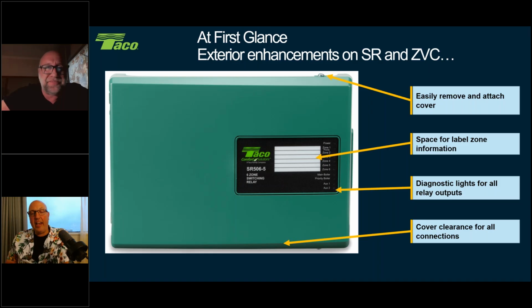Exactly. Yep. And somebody said to me today, why didn't you do this so long ago when you knew you had the error? Not the error, but you had the issue. And I said, well, because this is a UL approved control. You can't just go make one little change. Well, you could, but now you have to go in for 9 months of testing with UL. All right. And a big old fat check because it's a whole new design. It's not just that simple to redesign some of these things. So that's why we had this laundry list in order to do everything in one shot for you guys out there. All right. So what's under the hood?